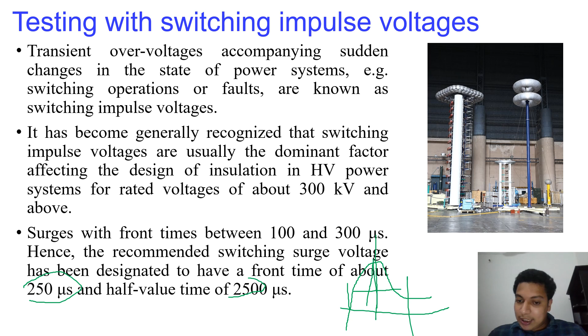With switching overvoltages, lightning is a very fast phenomenon, but switching overvoltages take longer: a 250 by 2500 microsecond wave. The peak time is reached in 250 microseconds, and the time to reach the tail value is 2500 microseconds. In lightning overvoltages, the peak time was reached in 1.2 microseconds. So that is the time difference.